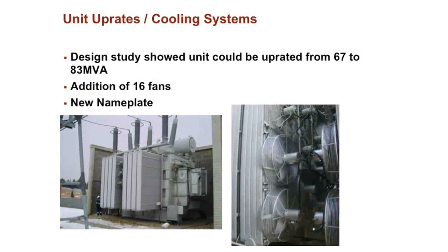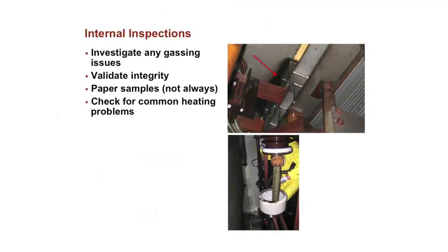This is an example of a cooling upgrade. In this case the old fans were taken away, and higher speed, higher capability fans were put on, and in this way you can reduce the oil temperatures. In this case, the customer wanted to increase the capacity of the transformer, but you could also do this just to lower oil temperatures so that you can reduce the cellulose aging. So this is a fairly inexpensive option. And then I talked about internal inspections. Again, this is very good if you have some kind of gassing in a transformer. You can often find what the problem is, and then do fixes on it.